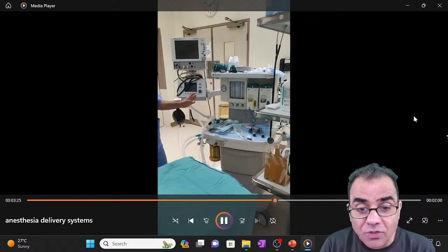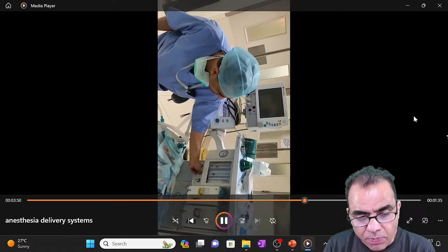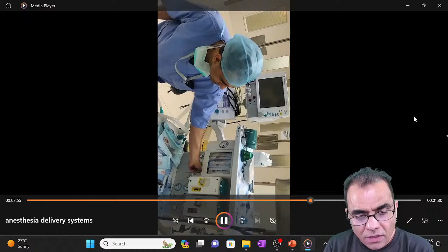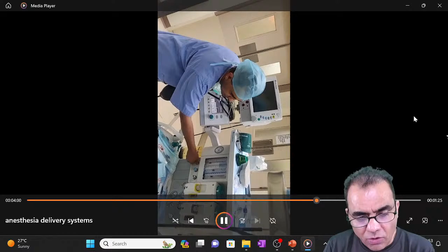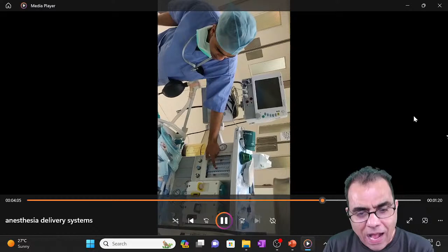Now I'm opening oxygen. Can you see this bobbin going up? Similarly, now I'm opening nitrous oxide. Can you see the bobbin is coming up, and I can set the flow to whatever I want. This tube is in milliliters and this is in liters. Now I'm opening air. Now I want to reduce oxygen by rotating this knob. This bobbin will go up or down, and the upper level of the bobbin will set the flow rate. So that is how we set the flow rates.